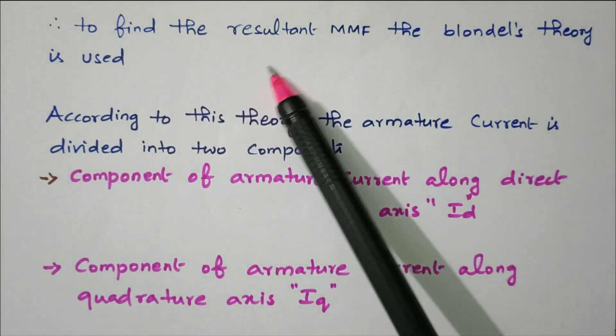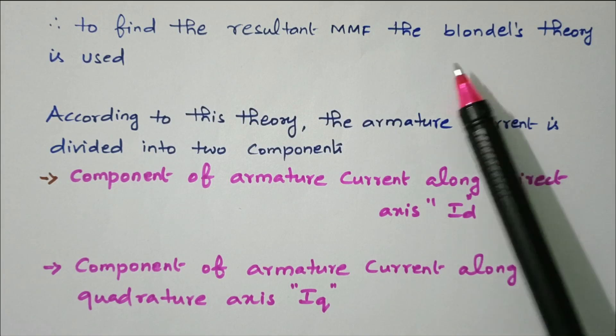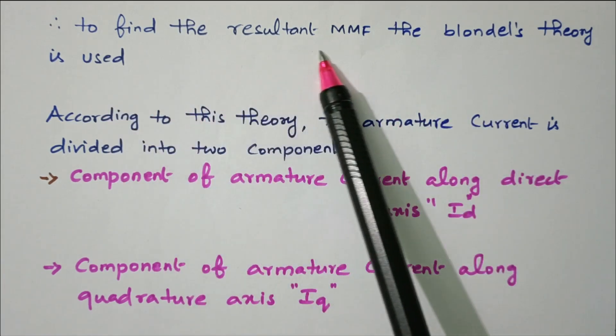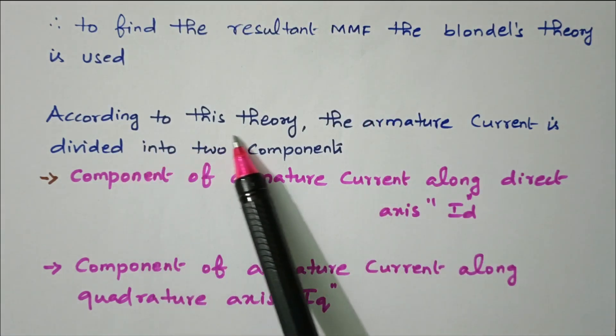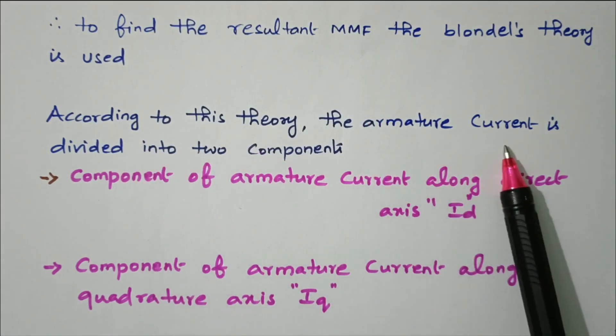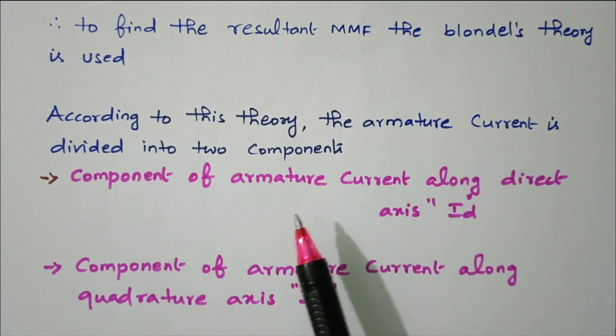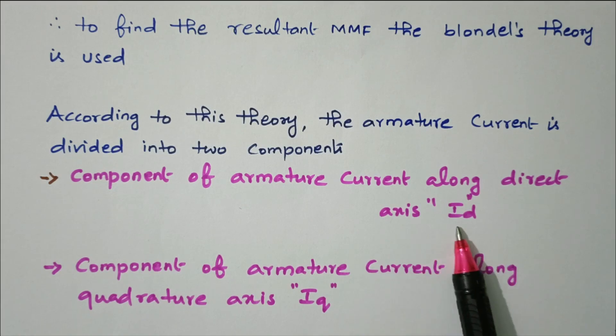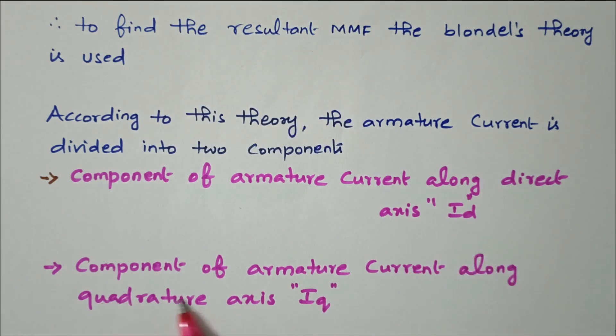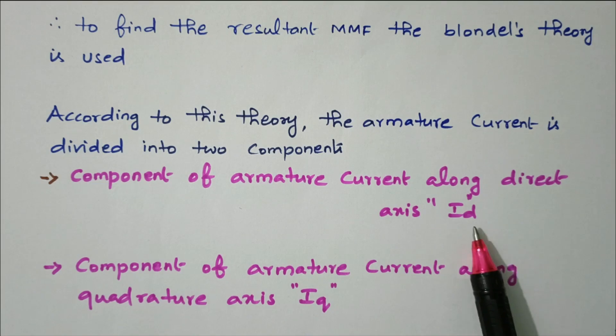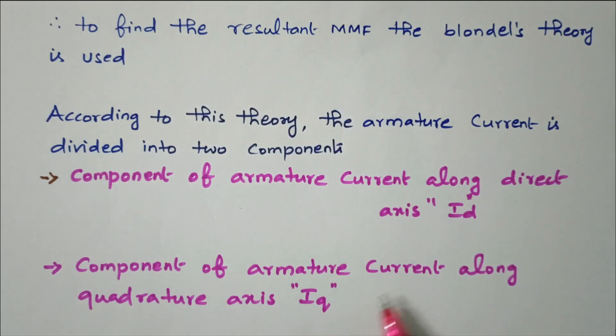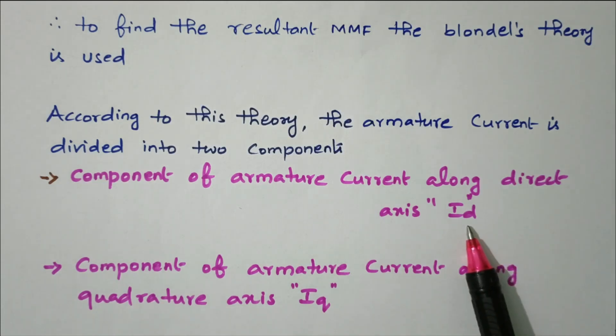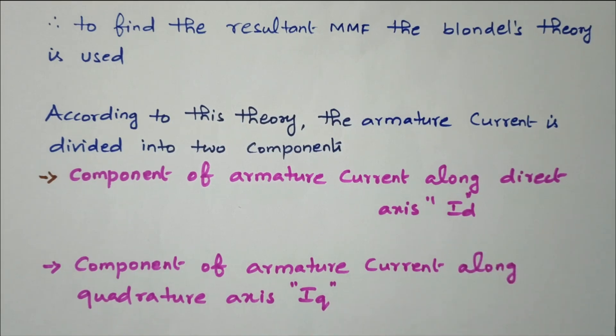To find the resultant MMF, Blondel's theory is used. According to this theory, the armature current is divided into two components: the component along the quadrature axis is Iq, and the component along the direct axis is Id. So the armature current is divided into Id along the direct axis and Iq along the quadrature axis.